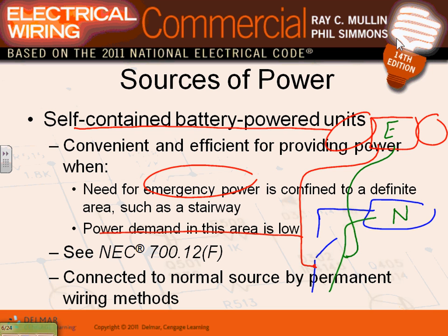If it senses that there's no power in this area, there's a little relay here that actually connects to a battery. There's a battery here, and that relay is tying the lights to the battery. It senses there is no juice coming out of the system, and it switches you into a tiny little battery that gets you, I can't remember, 80-some minutes, 90 minutes, something like this. It gives you an ample amount of light to get you out of the room.